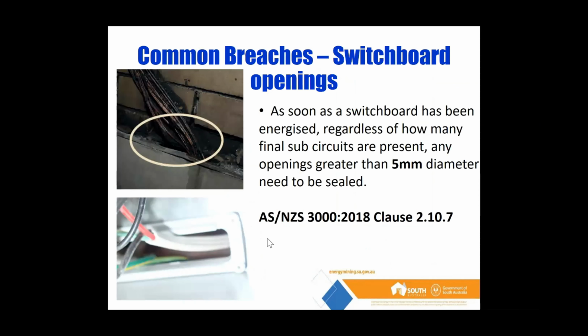This is probably the most common breach that all of us find when we're going out and performing our audits. And it's something that is even in our apprentice presentations when we undergo them at RTOs. What we constantly find is we call them apertures, however, they're more commonly known as openings in a switchboard aren't sealed correctly. Now what can happen in a switchboard, you can have a fire, and then the fire can then escape out of that switchboard, either up the wall cavity or out to other parts of the building, and it can actually engulf the entire installation.